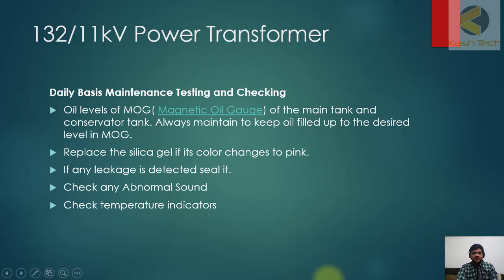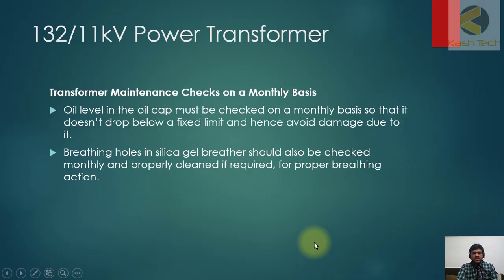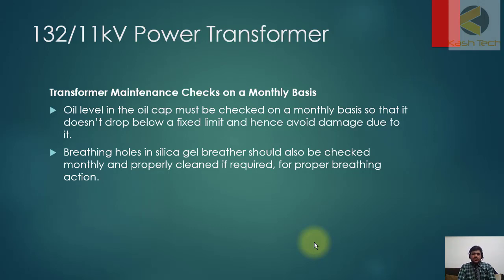On a monthly basis, the oil level in the oil cup must be checked so that it doesn't drop below a fixed limit, avoiding potential damage. As mentioned, in the breather there is oil below the silica gel — you have to check that oil too. If it is dirty, replace it; if it is less, fill it.